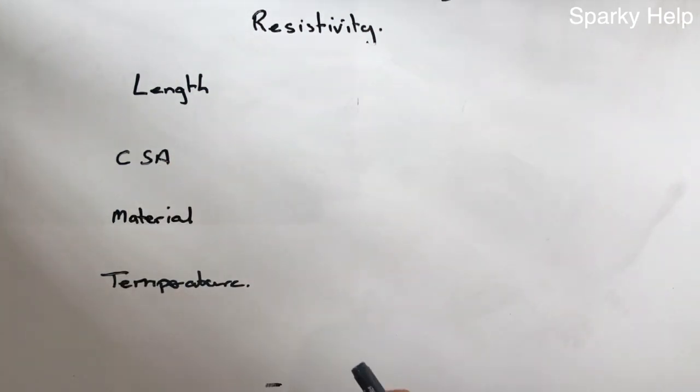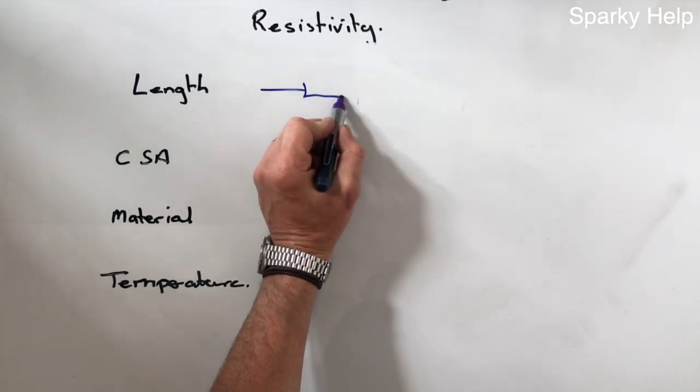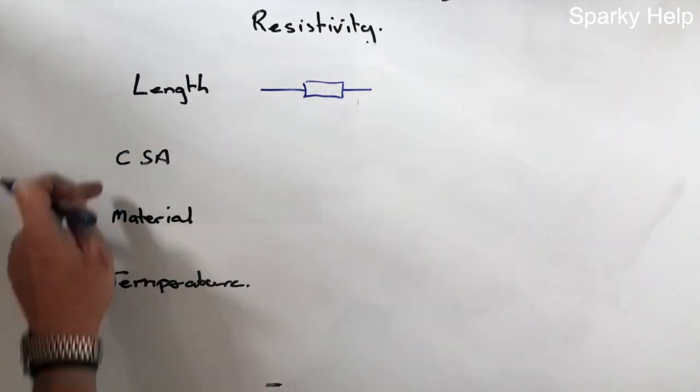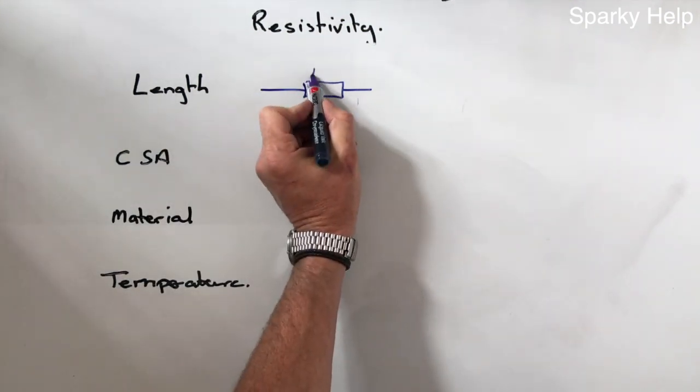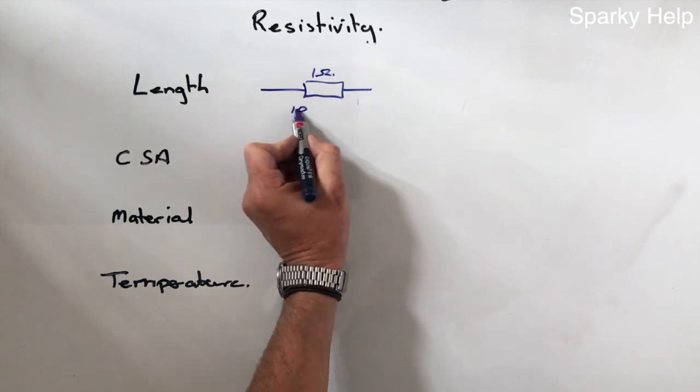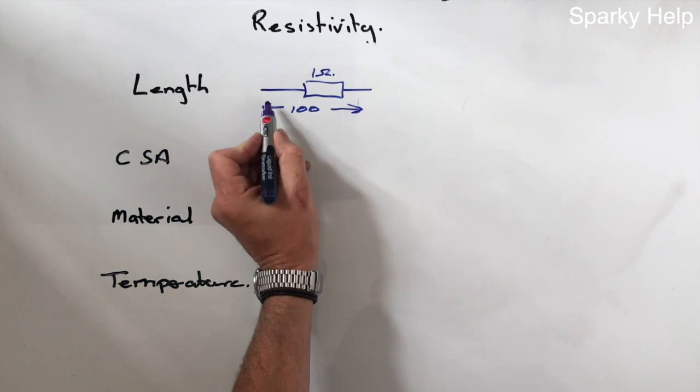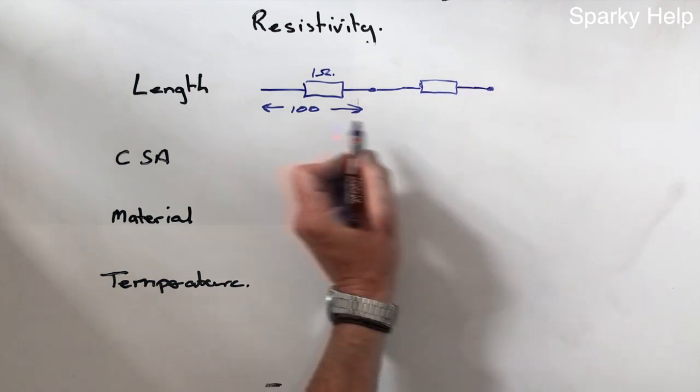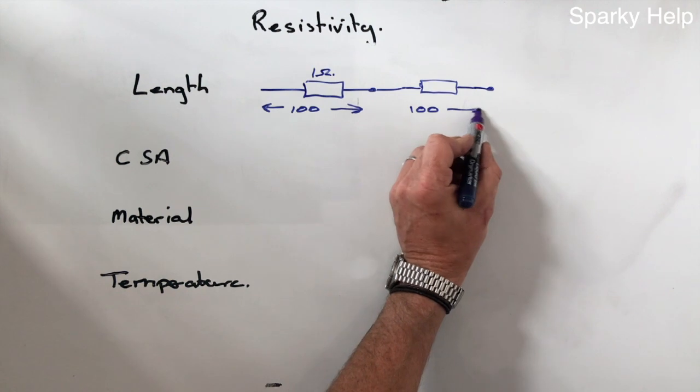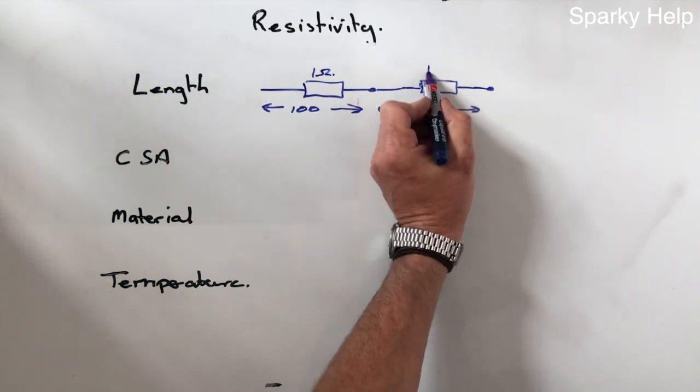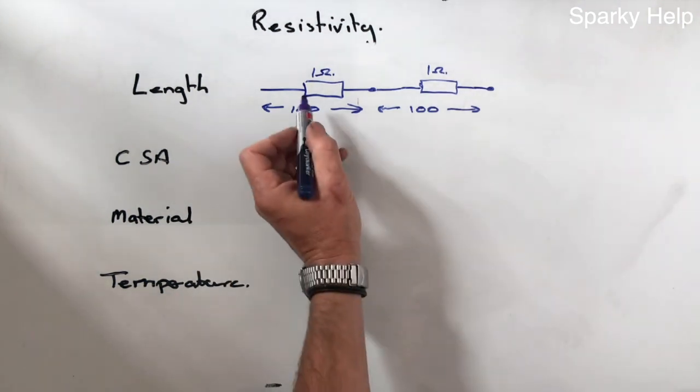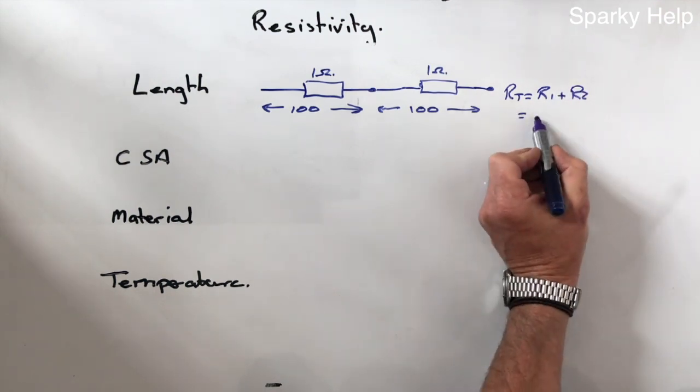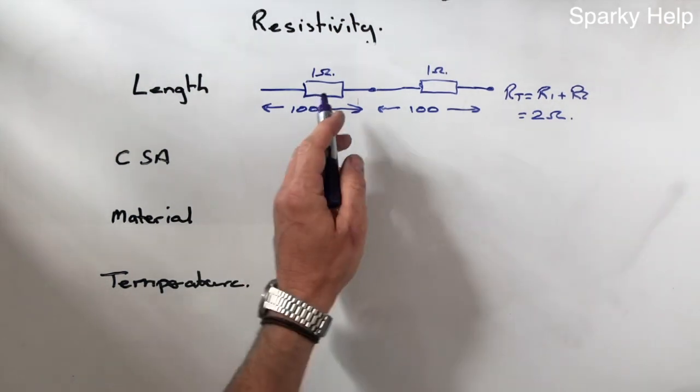In regards to length, we know that if we have a conductor that is 100 meters long, it will have a resistance, providing all of these things stay the same. Let's assume it has 1 ohm, and this relates to 100 meters in length. Then you join it onto another piece of cable, identical in length and size and material, and that also has 1 ohm. We know that RT therefore will be R1 plus R2, given a grand total of, for this example, 2 ohms.